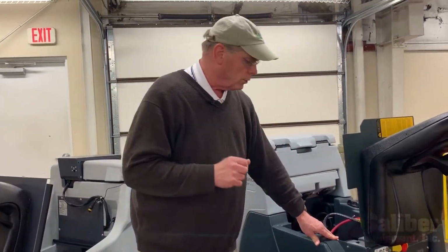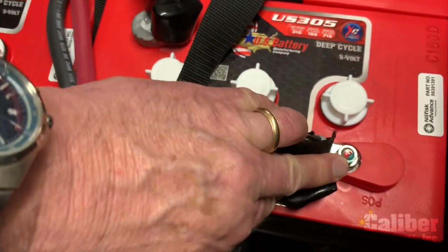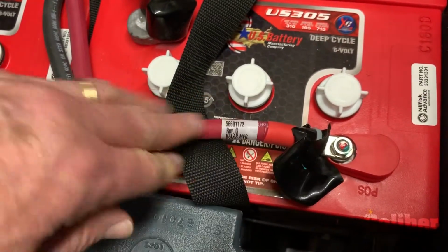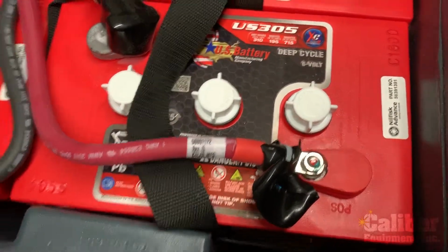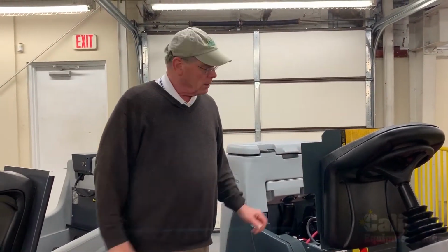There's nuts. Stephen, you can come over here and show that, please. These nuts have to be properly fastened and tightened, and if they're not, if there's a gap, if there's a looseness, then the electricity wants to jump from one spot to the other, creating a spark or an arc, and that's the thing that can set off the hydrogen, and that's the thing that can literally blow the top off these batteries and be dangerous to people. That's associated with lead acid batteries.